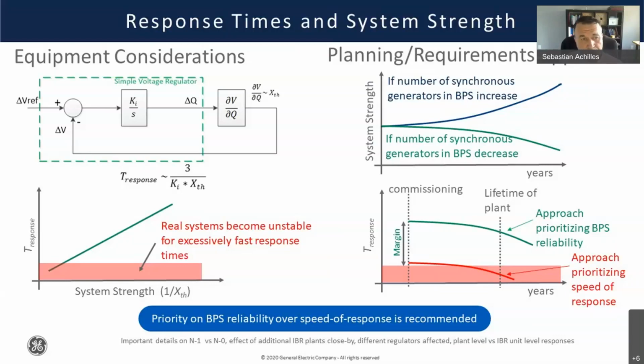If this loop is relatively simple, you can approximate its response time—for example, to a voltage reference change—using the equation shown below the diagram: 3 divided by the gain, divided by the system reactance. This is very basic, I know you all have lots of experience, but the main point is that the response time of this regulator is a function not only of the controller setting, but also of the system impedance.